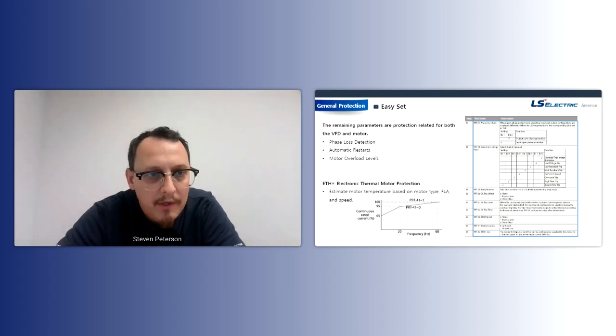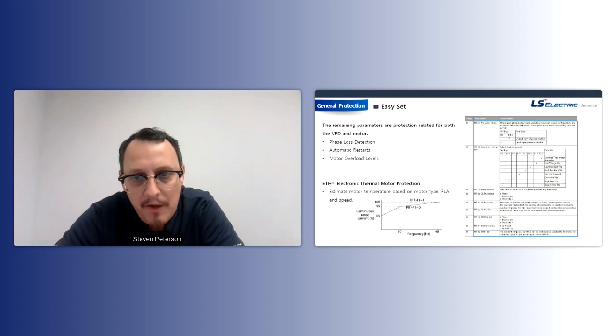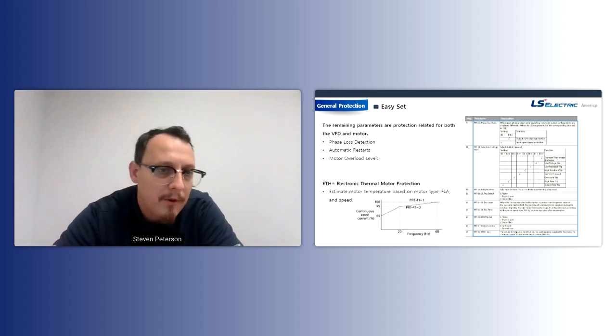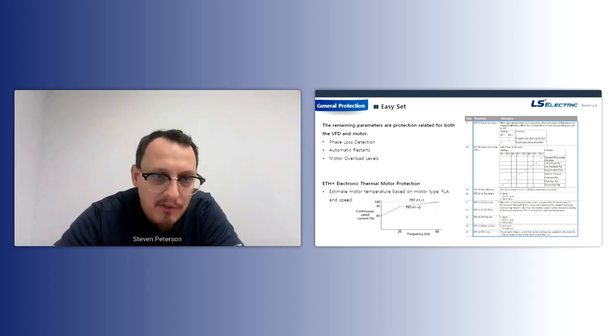Additionally, we could enable automatic resets on the drive. So you could set up to 10 automatic resets. So if the drive ever trips out, a lot of times for pumping stuff, people just set it and forget it. If it trips out, they want it to at least do some kind of restart. So you could scale that anywhere from 1 to 10 automatic restart attempts.